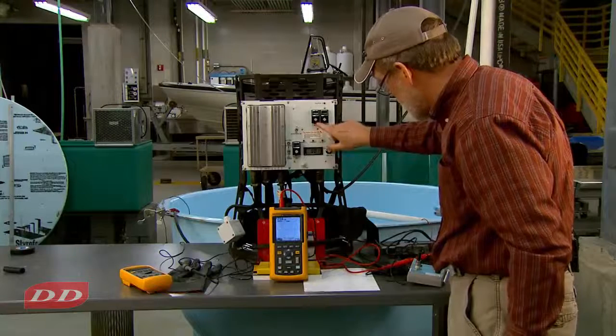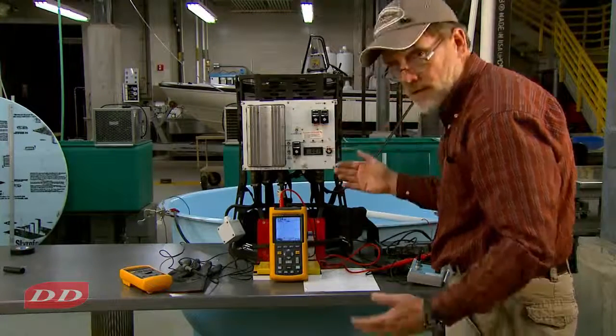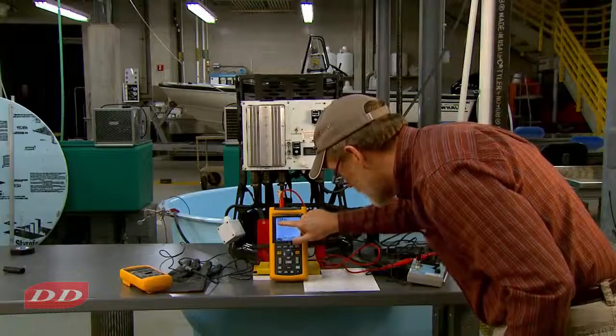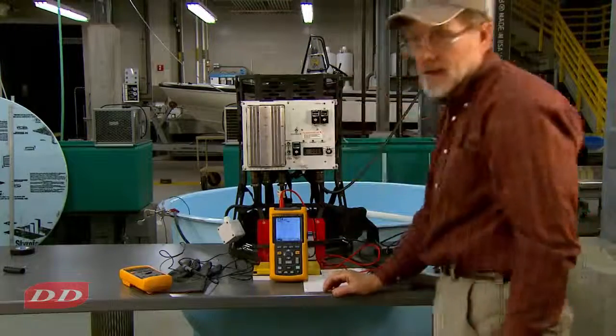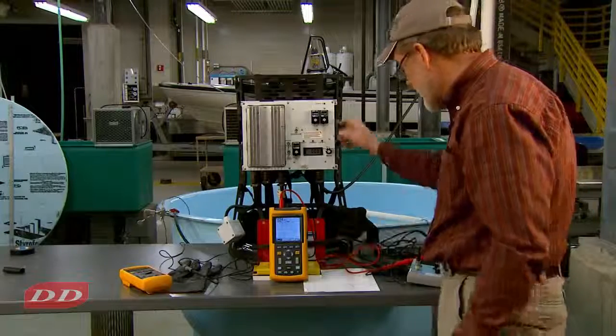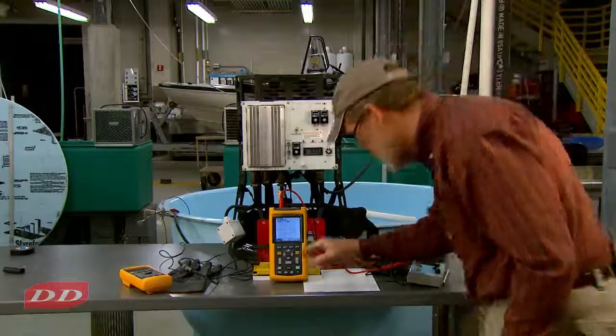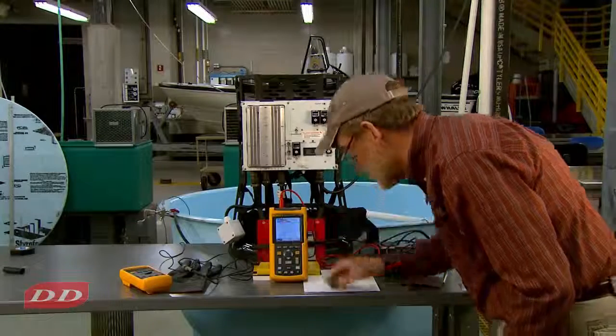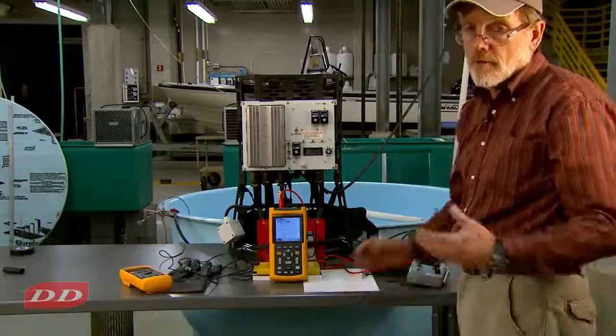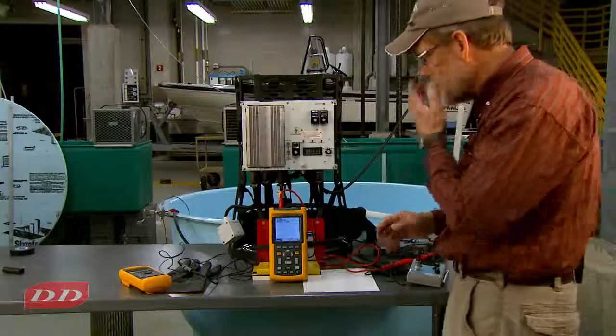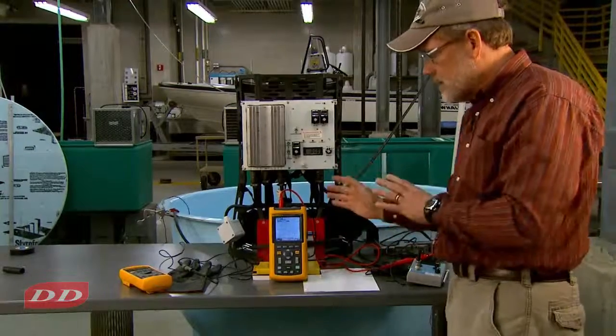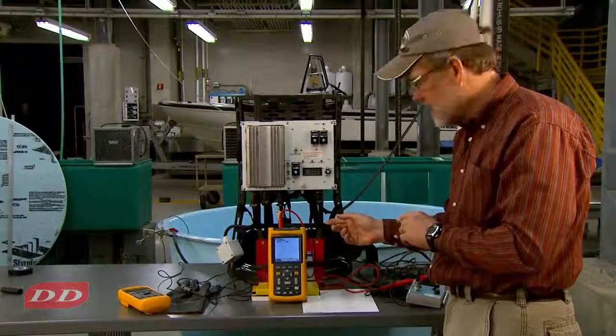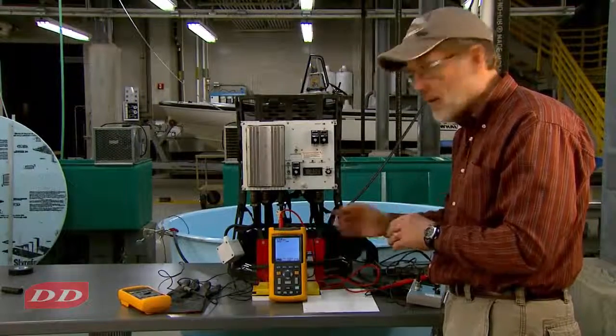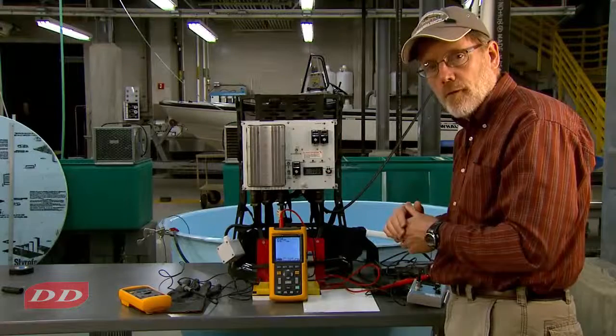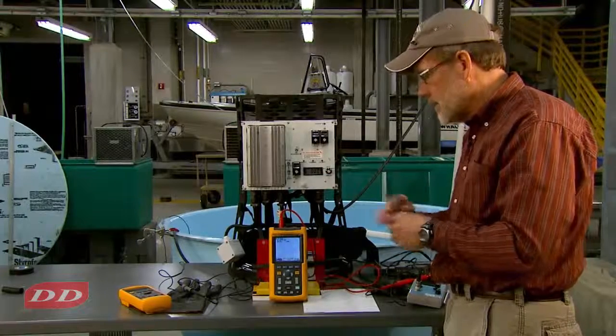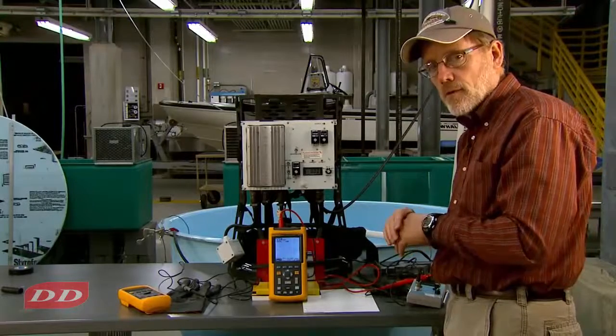So we look at the waveform that we set in again. We put in a frequency, a rate of 60 hertz or 60 pulses per second. The waveform actually came out a little over 59, so that's a good match. And we had a 24% duty selected, and we see that the duty measured was 23.4%. So a very good correspondence there. So now I'm going to change out the multimeter for the oscilloscope or scope meter, and then progress on for a few more voltage readings, so you can see how that piece of equipment works.